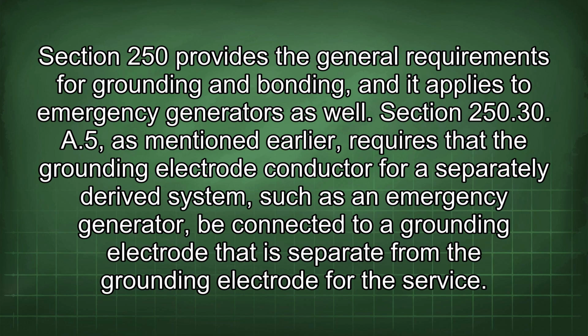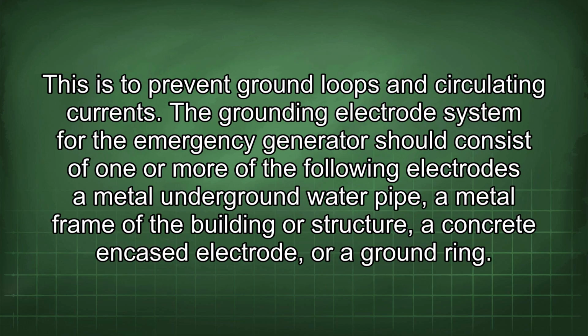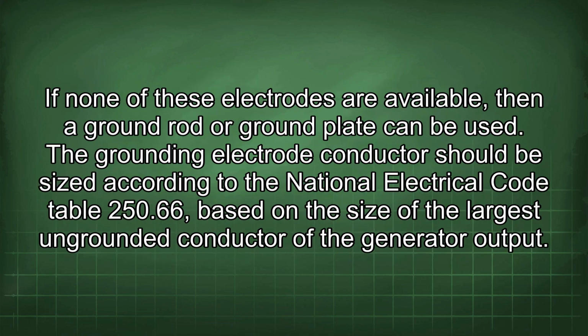Section 250.30 A5, as mentioned earlier, requires that the grounding electrode conductor for a separately derived system, such as an emergency generator, be connected to a grounding electrode that is separate from the grounding electrode for the service. This is to prevent ground loops and circulating currents. The grounding electrode system for the emergency generator should consist of one or more of the following electrodes: a metal underground water pipe, a metal frame of the building or structure, a concrete encased electrode, or a ground ring. If none of these electrodes are available, then a ground rod or ground plate can be used.